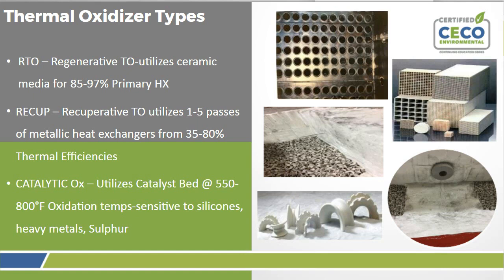Thermal oxidizer types, the three major types that we see besides the direct fired are typically the RTO. That's been the most flexible through probably the last 2 or 3 decades. The regenerative thermal oxidizer regenerates various beds, typically 2 to 9 or 11 beds, depending on the design. And you can get between 85 and 97% primary heat recovery.